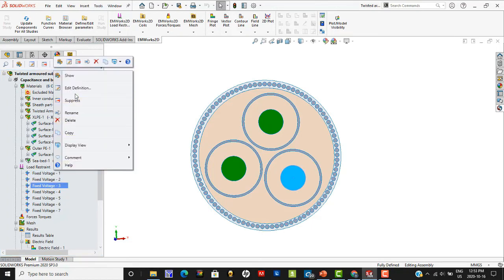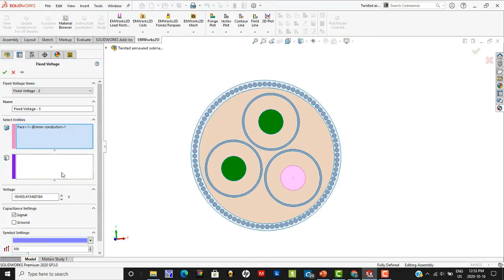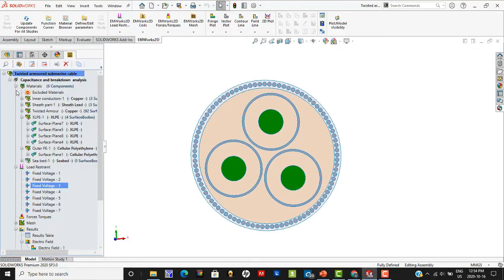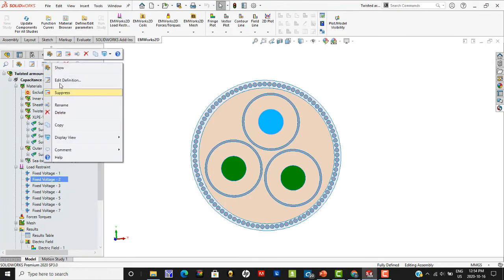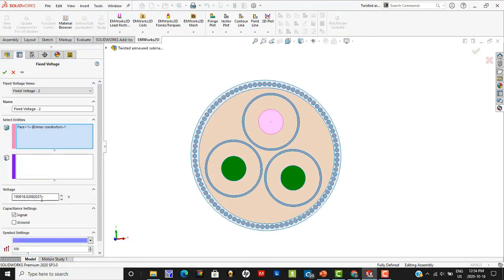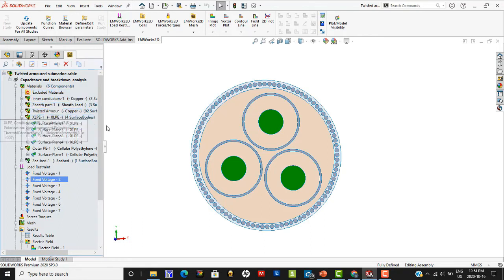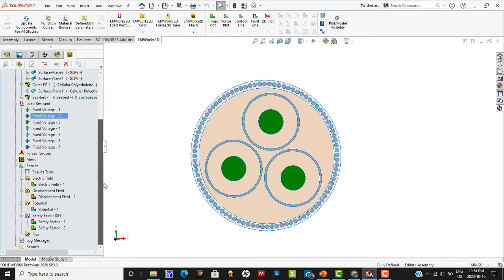Each of these conductors has a particular potential. When carrying three-phase voltage, two conductors might have 95,000 volts and one conductor could have twice that — 190,000 volts. This worst-case scenario has been studied in this simulation, where one cable has a positive potential and two cables have negative potentials equal to half of that positive potential in magnitude.